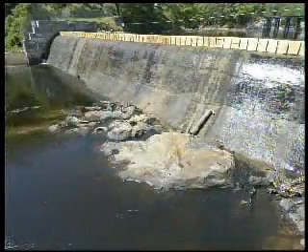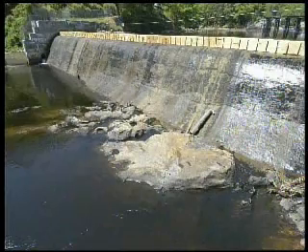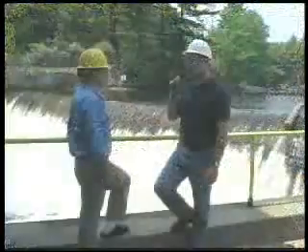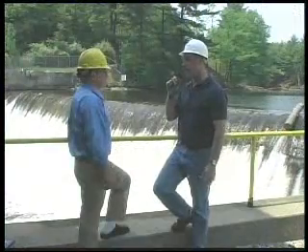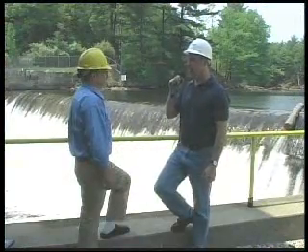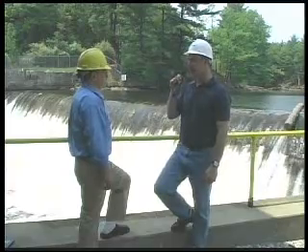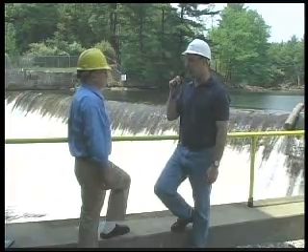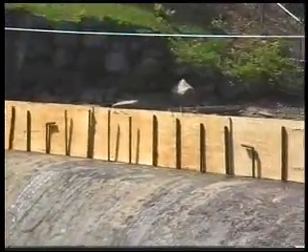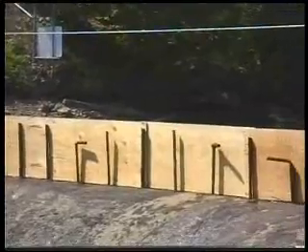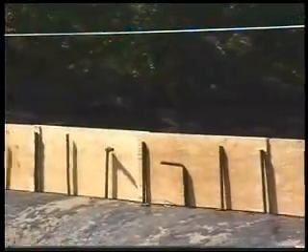Flashboards are put in place once we have control of the river, which is less than our hydraulic capacity. And what you'll be seeing here very shortly, within the next week, we'll probably end up putting the flashboards up. Essentially, we draw it down just a few inches below the dam crest and put pins in holes within the dam, pin sockets. Once they're in place, the flashboards are attached to those pins. And that's where they stay until a high water event.